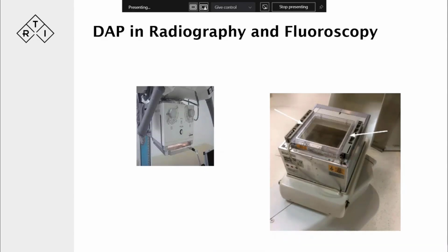So from our point of view, this may be something that we could verify and check against to calibrate and verify the output of a DAP chamber like this. And of course, we could do it in tandem or work it with the dose probe, looking at the beam size. So there are different ways of doing it. So that's two examples of it.